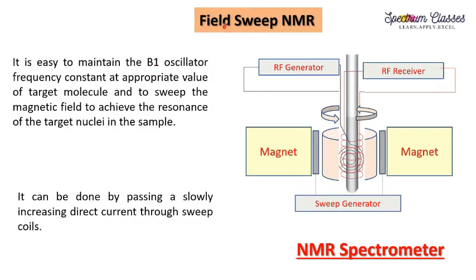Now we will discuss the field sweep NMR spectrometer. Field sweep NMR spectrometers are easier to handle because it is easy to maintain electronically the B1 oscillator frequency constant at an appropriate value for the target molecule, and to sweep the magnetic field to achieve resonance of the target nuclei. In this case, we keep the RF oscillator frequency constant and change the B0 field.